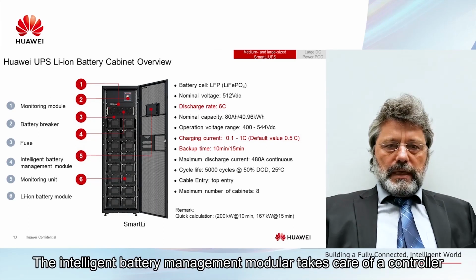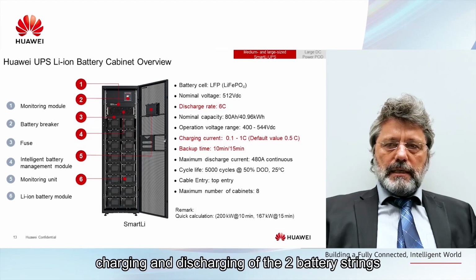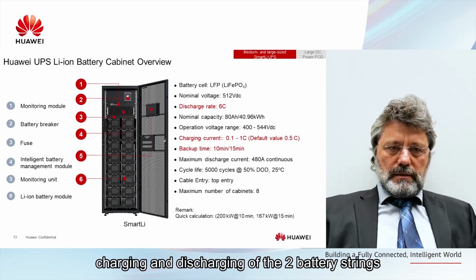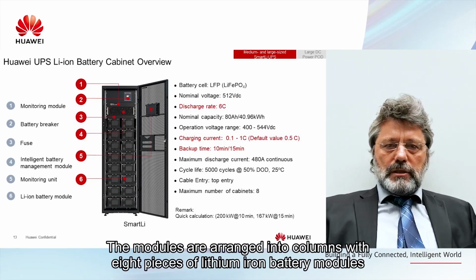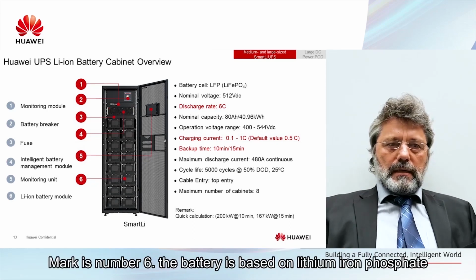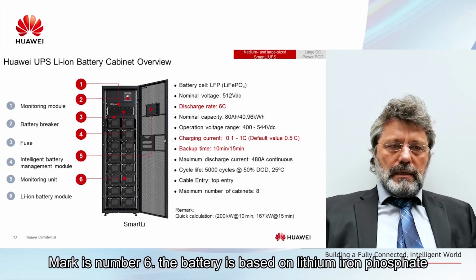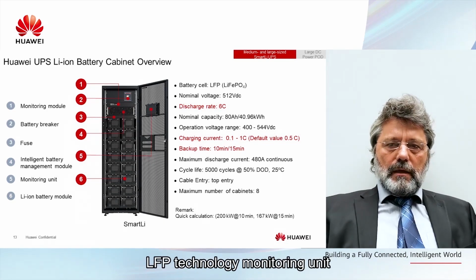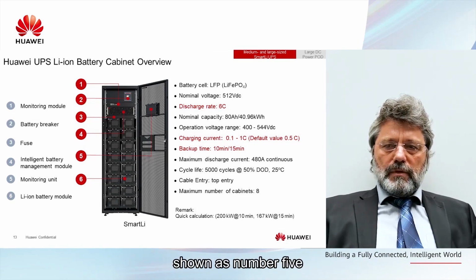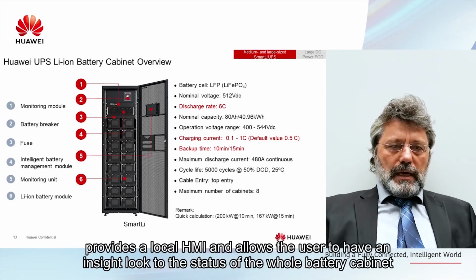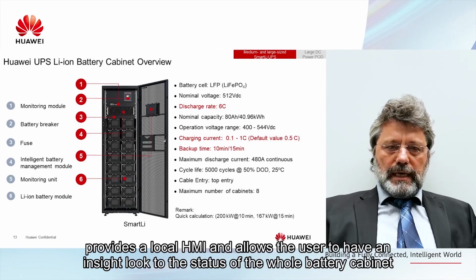The intelligent battery management module takes care of a controlled charging and discharging of the two battery strings. The modules are arranged in 2 columns with 8 pieces of lithium-ion battery modules marked as number 6. The battery is based on lithium iron phosphate LFP technology. The monitoring unit, shown as number 5, provides a local HMI and allows the user to have an inside look at the status of the whole battery cabinet.